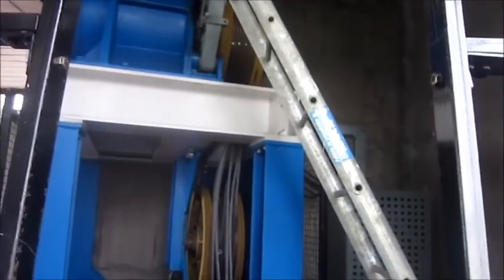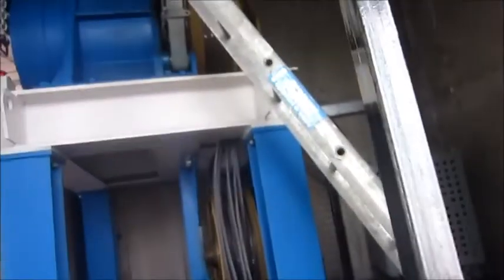So you've got a rotor and a stator on a motor, as I'm sure you know, and the windings on the stator are burnt because, well, you can argue all day long about why they've got burnt. We had the ropes off during the week, and on Wednesday of next week someone is coming down, and we're going to help them split the motor in half, and with a bit of luck, get some of it in the lift and down to the bottom so it can go off and be rewound.